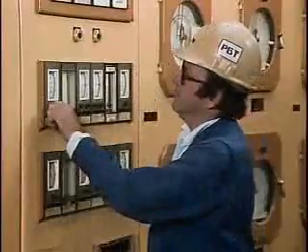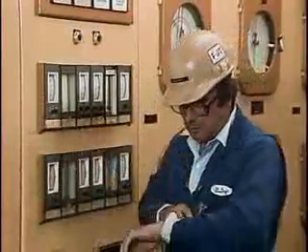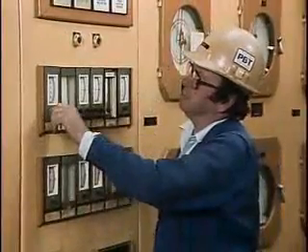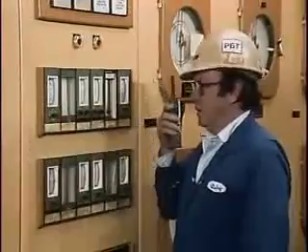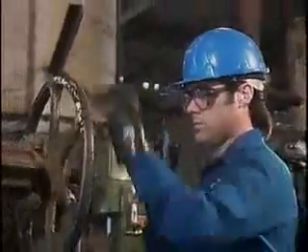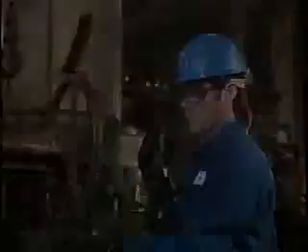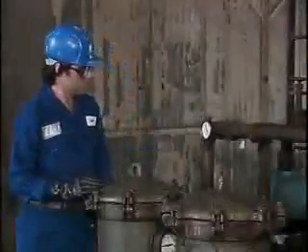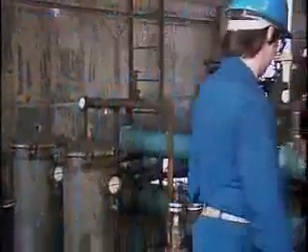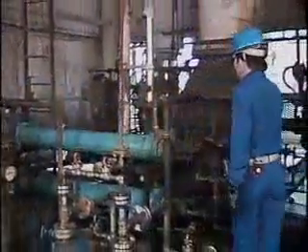Once the compressor has been purged, it is started and allowed to warm up. The steam turbine is started at a low speed to allow the compressor to warm up. The steam turbine is started by opening the steam supply valve. As the compressor is warming up, it's important to make sure that the proper flow of cooling water is maintained to the lube oil cooler.